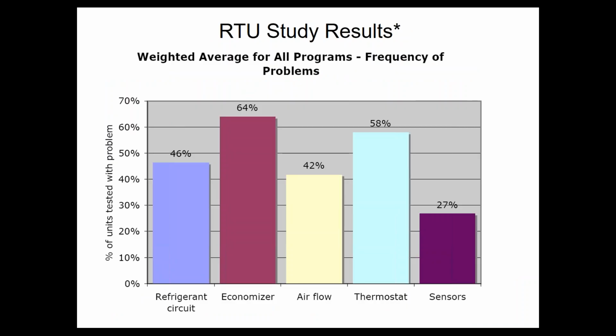The other problem with economizers, and you guys have probably seen this in other classes that I've done, is that economizers historically don't work. Right? They work. The technology works, the concept works, but things get broken. People screw them shut, people jam them open to get temporary airflow through there. Linkage arms get loose and sloppy. The settings get programmed incorrectly or adjusted or manipulated.